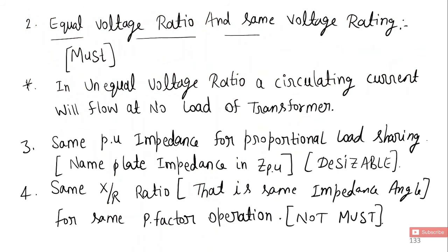Number two: Equal voltage ratio and same voltage rating. This is also must. If the transformer rating is 4000 by 400, for example, both transformers must contain the same voltage ratio.